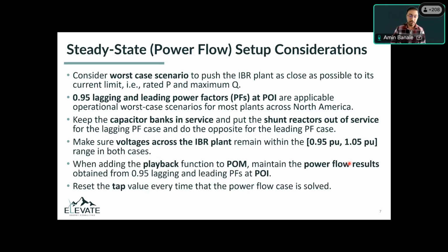And then finally, make sure to reset the tap value every time that you solve a power flow case, specifically in PSSE and PSLF, since that tap changer is going to regulate the MV side voltage. And when you are trying to set up 0.95 lagging and leading cases, you may see over voltage, but you have not reset the tap. And when you do that, that over voltage is going to be gone.